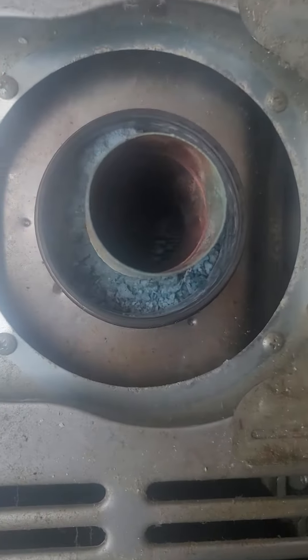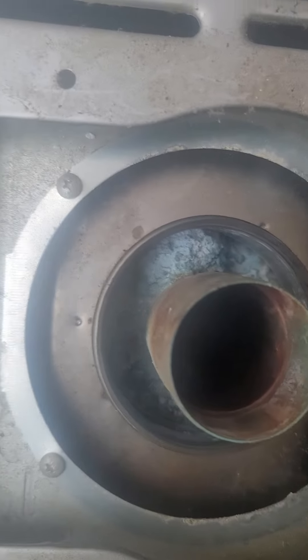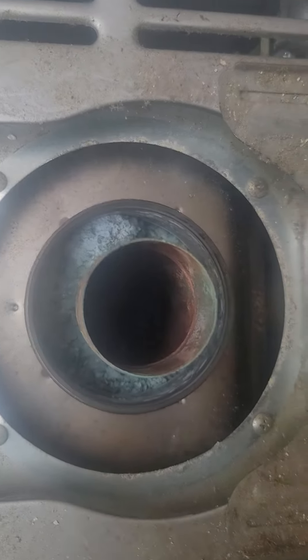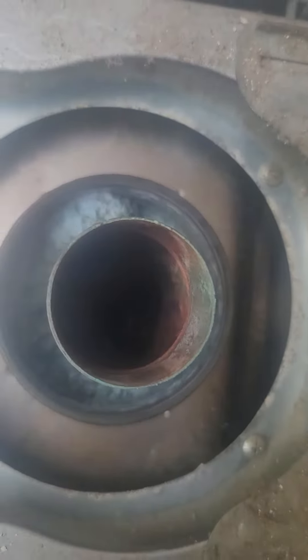This is a tankless water heater with a concentric vent. That's our exhaust, and this is our fresh air. See all that green stuff? That's water that's been accumulating because it hasn't been venting right. It wasn't breathing — it was making carbon monoxide. I've never seen one that bad.